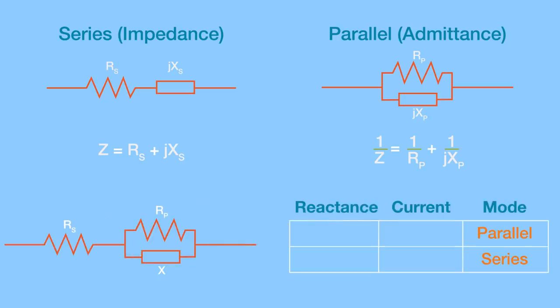These confuse the meter, so sometimes we have to help it understand how to interpret what it is measuring. If the device under test has a large reactance, then the current should be small, meaning the series resistance is less critical. In that case, the parallel mode is probably more accurate. On the other hand, if you have a small reactance, then the current is going to be relatively high, and the series resistive element is more critical, so use the series mode.